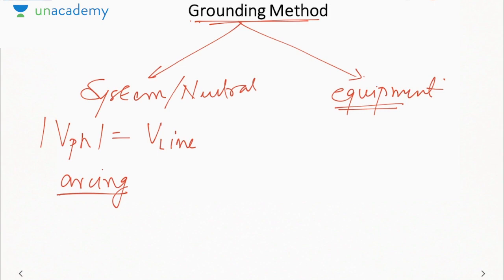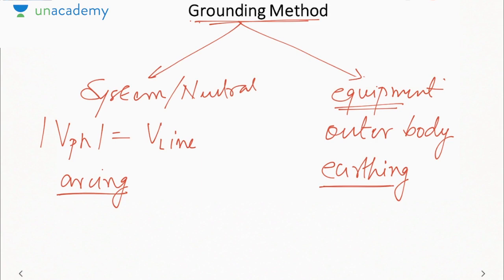Then what is meant by equipment grounding? It means grounding the outer body of the equipment. Now, why would we want to ground the outer body? Because there are certain stored charges on the body of every equipment. If there are stored charges, then what will happen? Whenever we touch the equipment, those stored charges will flow to the ground through our body. If those stored charges are flowing to the ground through our body, then we may get a shock. So to avoid that shock, we need to provide a path for the flow of those stored charges to the ground. That is done by equipment grounding, which is also called earthing. Okay. So this is the basic difference between the grounding and the earthing.